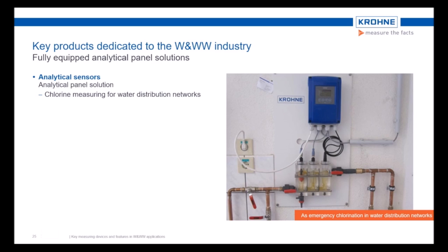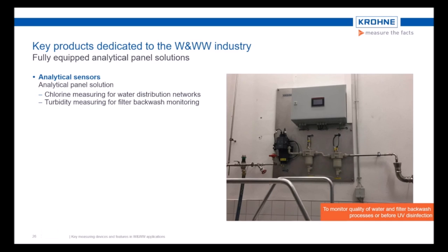The unique self-cleaning system of the chlorine sensor makes it independent of the cycle to be really used, and therefore the sensor is always ready to operate. Those pre-installed analytical boards are available in almost all variants customers are requiring. On that slide we see a solution with a turbidity measurement, which is used to monitor the quality of water behind a filter. The operator can control the filter backwash processes based on those values.